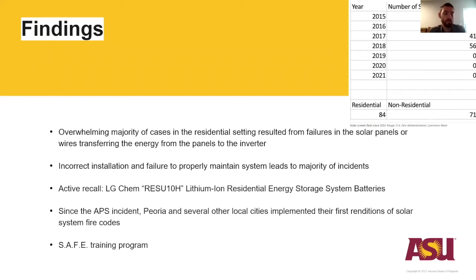My overall findings: the overwhelming majority of cases in the residential setting resulted from failures of the panels or the wires transferring energy from the panels to the inverter. This is not to say the battery cannot be a cause of the problems, but the overwhelming majority of them are not battery related. In the cases where batteries are the problem, it's typically a result of installation issues, either incorrect installation or failure to properly maintain the battery system, which can lead to degradation and failure of the battery.